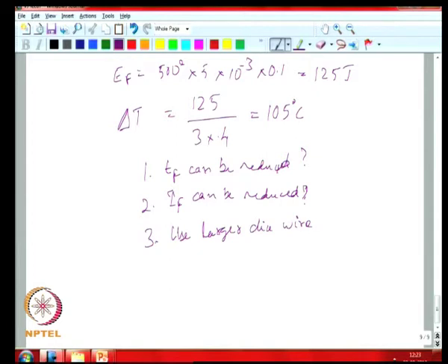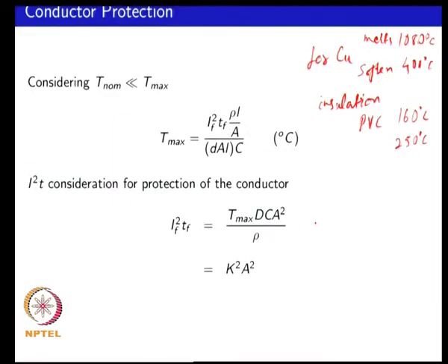the fault withstand capability of the wire, the parameter K that you saw in the expression over here depends on a number of factors. It depends on the material, whether it is copper, aluminum or some other alloy. It depends on your insulation.